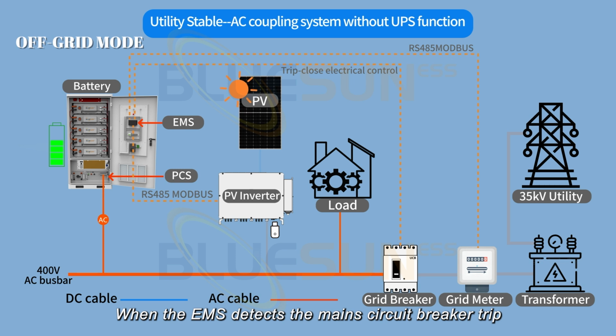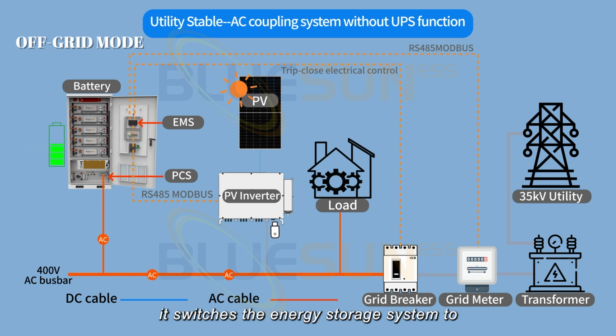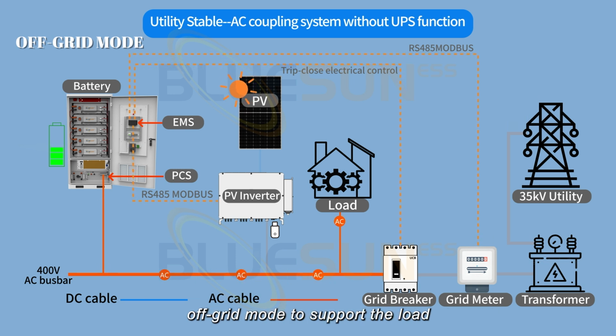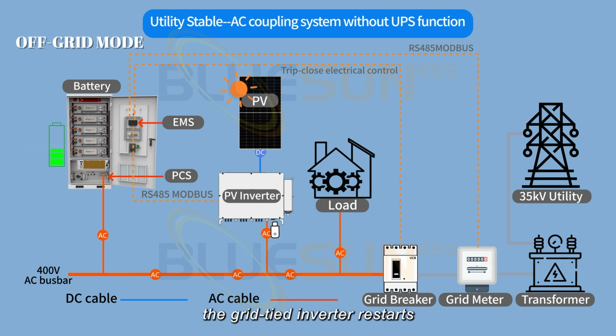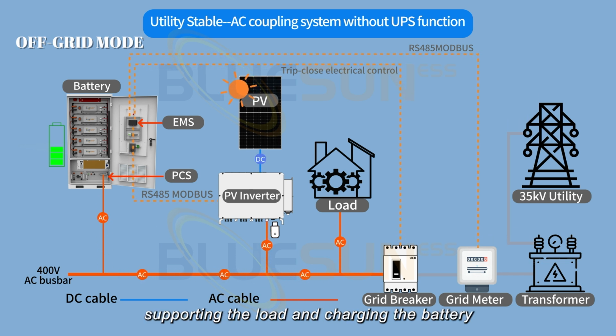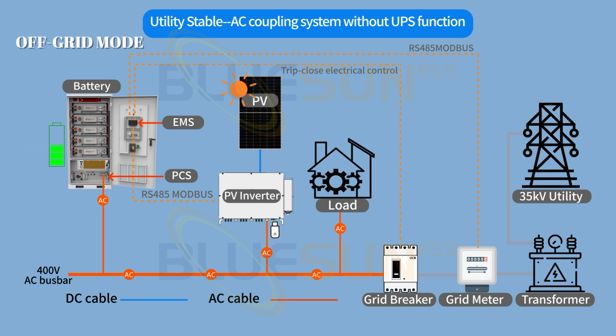When the EMS detects the mains circuit breaker trip, it switches the energy storage system to off-grid mode to support the load. After approximately 5 seconds, the grid-tied inverter restarts, supporting the load and charging the battery.